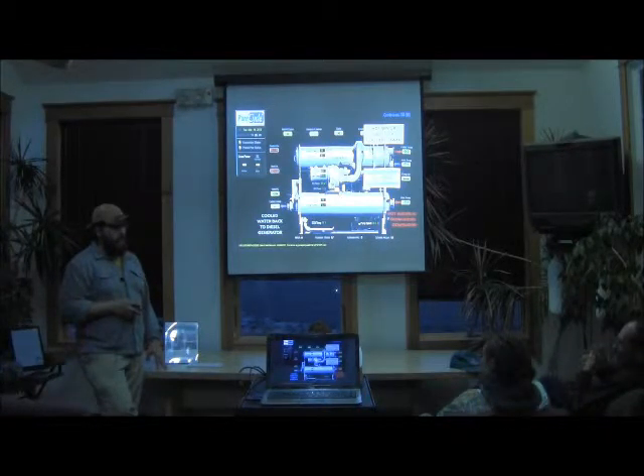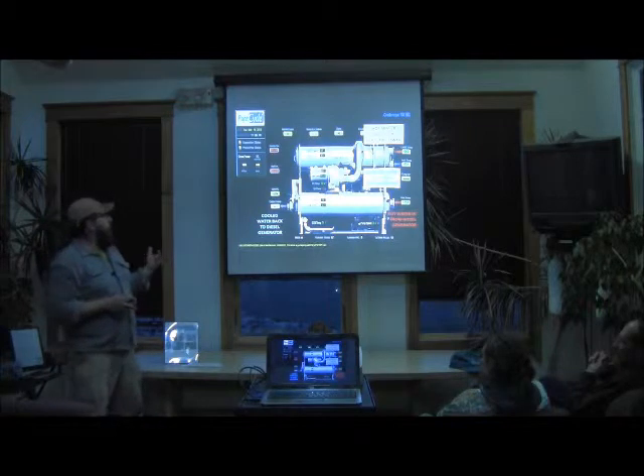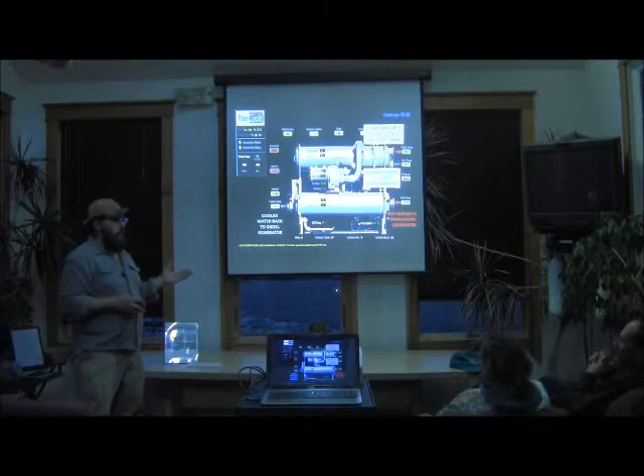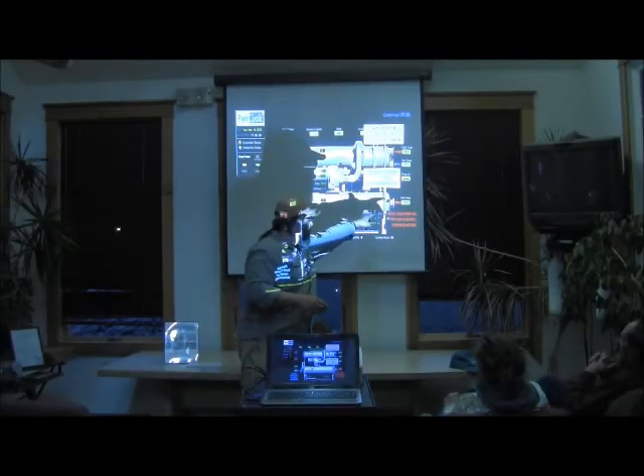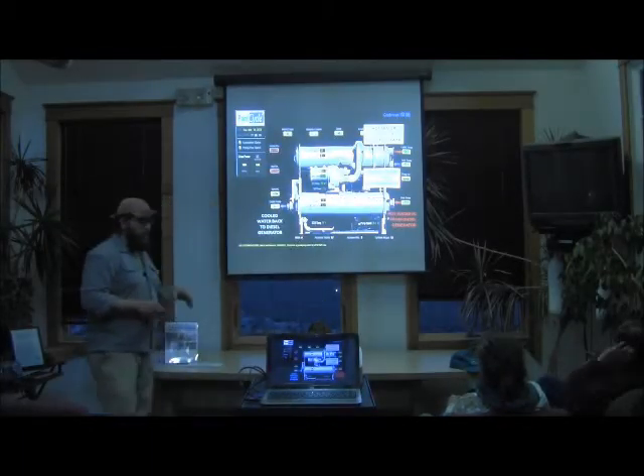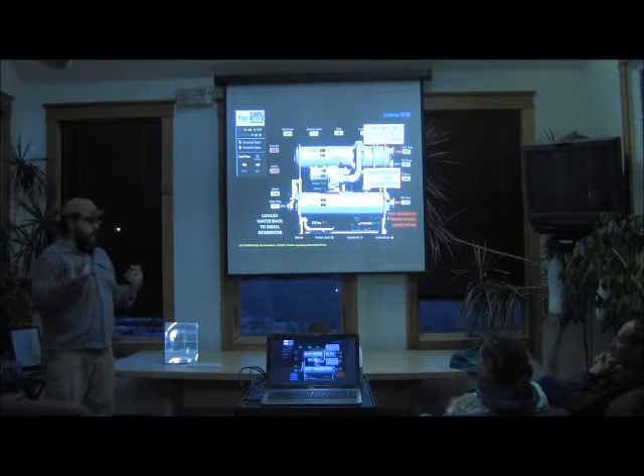You're gonna have to assume that you're gonna get no support whatsoever. Right now it runs, but we're not getting the optimal performance out of it that we should. The two things you need to look for are the inlet temperature needs to be around 190 degrees, and you need the right amount of flow. If it's flowing too fast, you can't pull the heat out of that water.